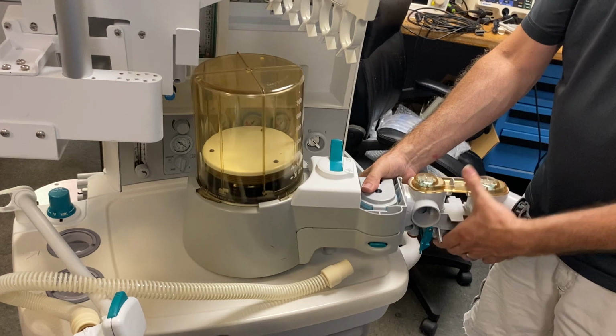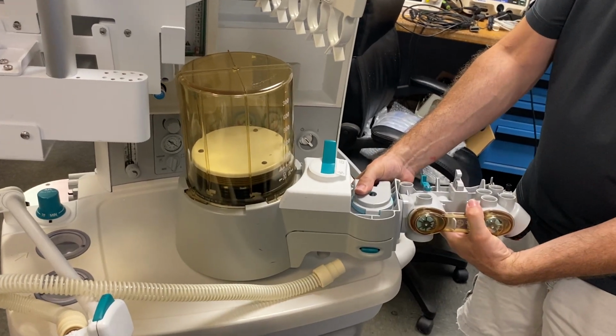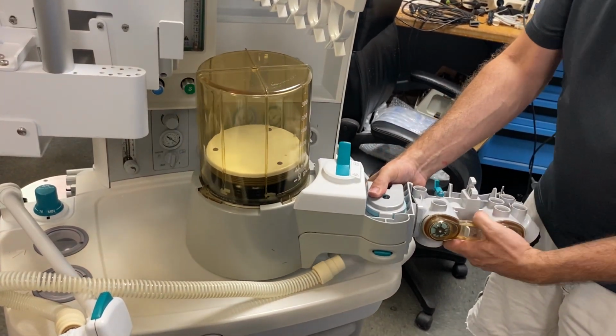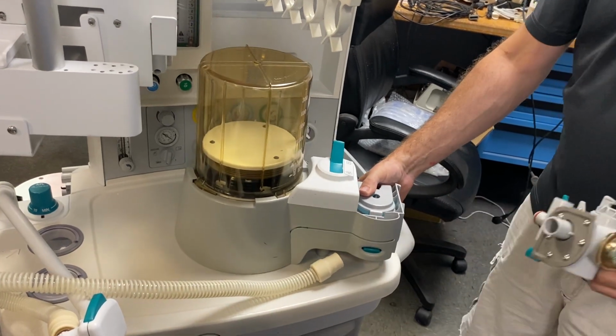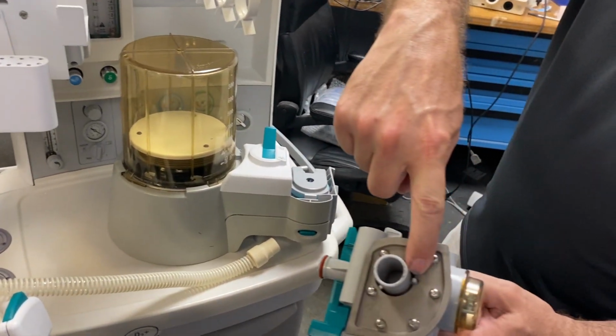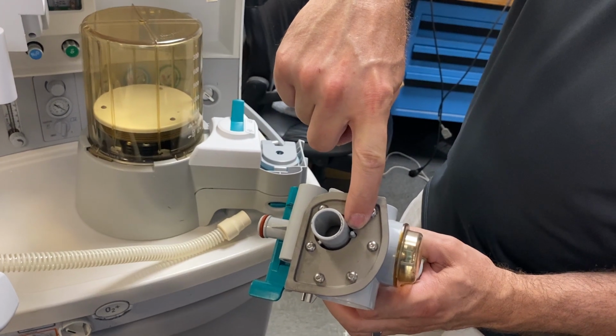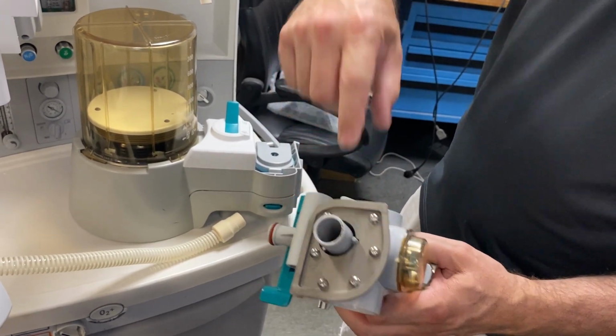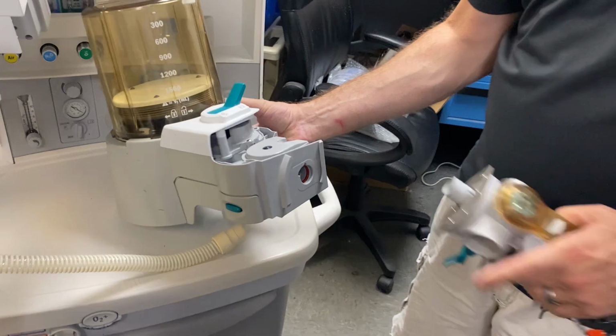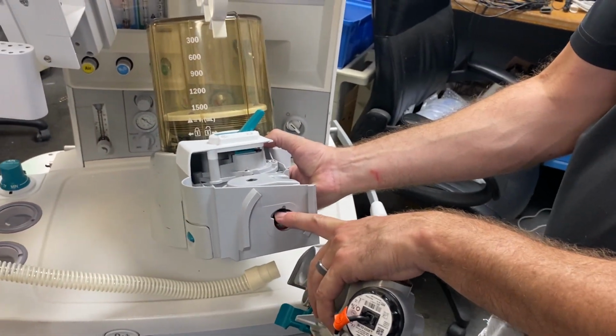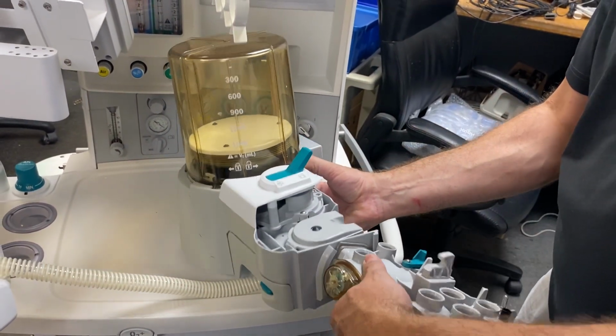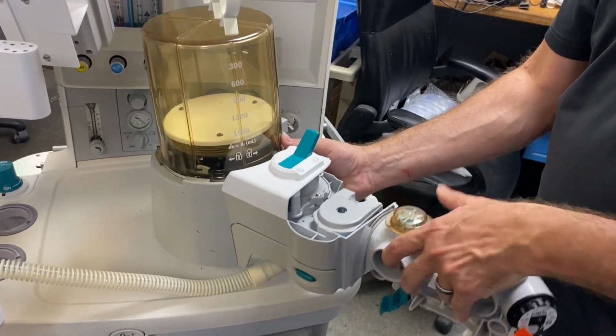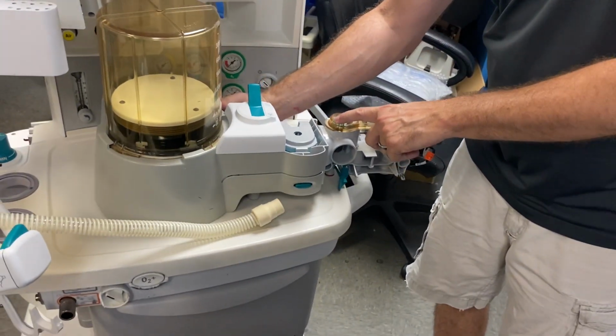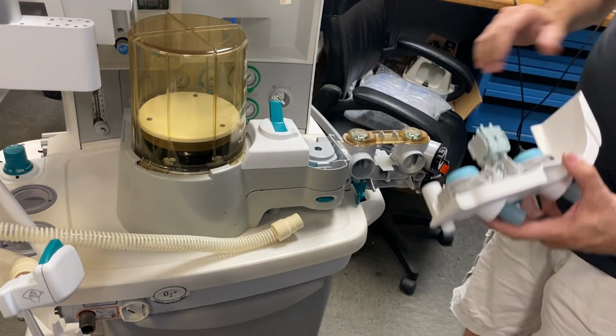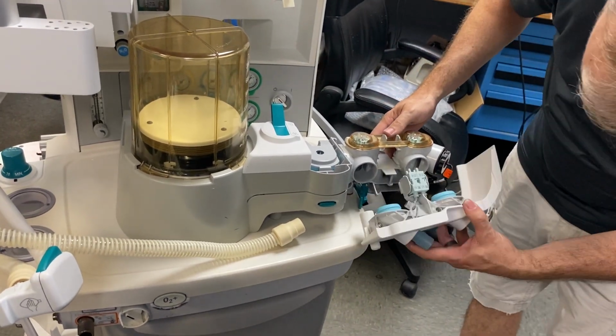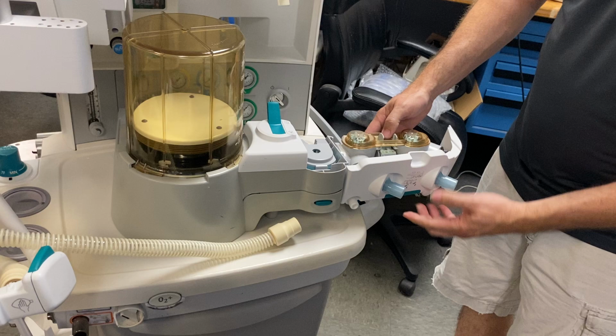You're just going to rotate this a half a turn. Pull it out. On the new one, if you notice, there's a plastic tip here, like a guide, a starting point. When you go to put the new one on, you'll see the notch for the tip. Just put that in, rotate it back until the flappers are pointing straight up. Insert your flow sensor module back in, lock it in place.